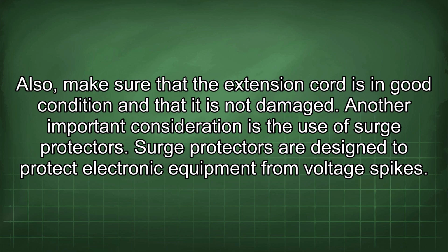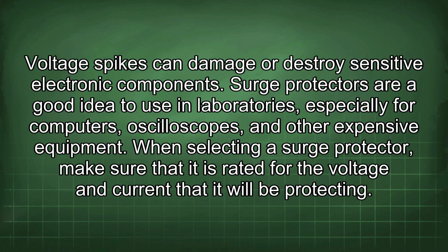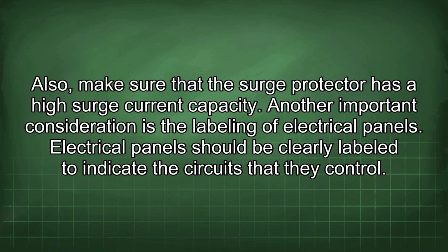Another important consideration is the use of surge protectors. Surge protectors are designed to protect electronic equipment from voltage spikes. Voltage spikes can damage or destroy sensitive electronic components. Surge protectors are a good idea to use in laboratories, especially for computers, oscilloscopes, and other expensive equipment. When selecting a surge protector, make sure that it is rated for the voltage and current that it will be protecting. Also, make sure that the surge protector has a high surge current capacity.